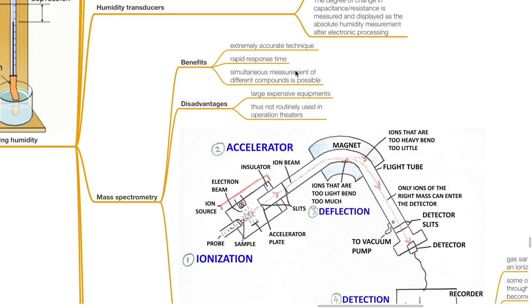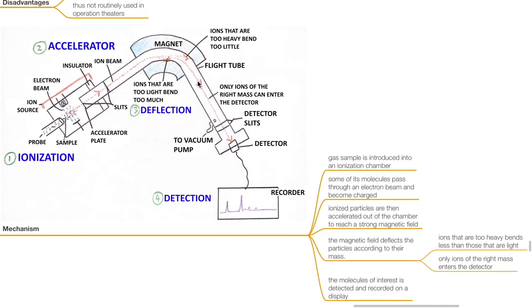Mass spectrometry. Benefits include: it is extremely accurate, has a rapid response time, and simultaneous measurements of different compounds is possible. Disadvantages include: it is large and expensive and thus not routinely used. Mechanism of action: a gas sample is introduced into an ionization chamber; some of its molecules pass through an electron beam to become charged; ion particles are then accelerated out of the chamber into a strong magnetic field; the magnetic field deflects the particles according to their mass — ions that are too heavy bend less than those that are light; only ions of the right mass enter the detector, and the molecule of interest is detected and recorded on a display.